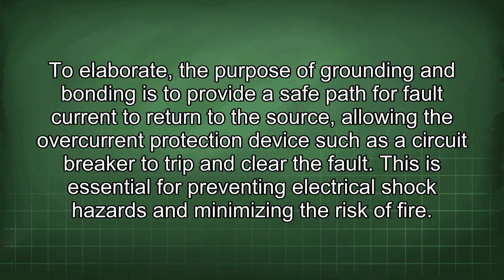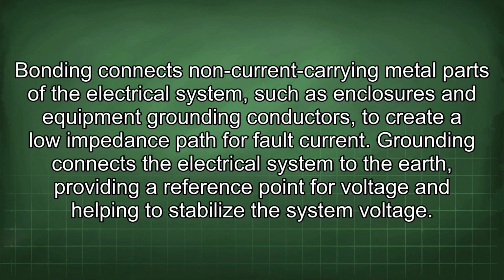To elaborate, the purpose of grounding and bonding is to provide a safe path for fault current to return to the source, allowing the overcurrent protection device, such as a circuit breaker, to trip and clear the fault. This is essential for preventing electrical shock hazards and minimizing the risk of fire. Bonding connects non-current carrying metal parts of the electrical system, such as enclosures and equipment grounding conductors, to create a low impedance path for fault current.